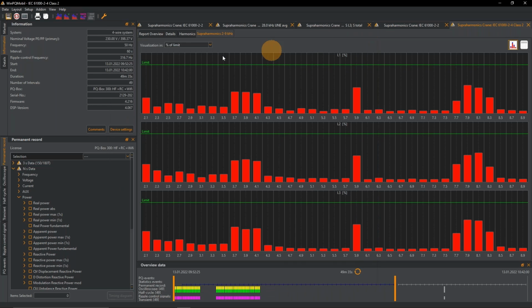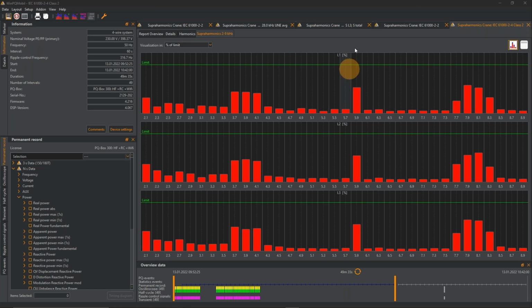You cannot change the limit values for generating dips, swells, and interrupts, because they rely on settings that are valid while recording. So like I said, the only trade-off is dips, swells, and interrupts. You cannot change these thresholds afterwards, because they generate events while they're recording.